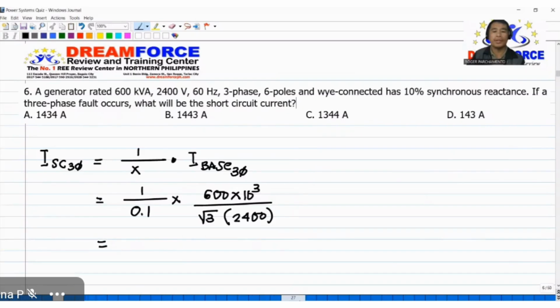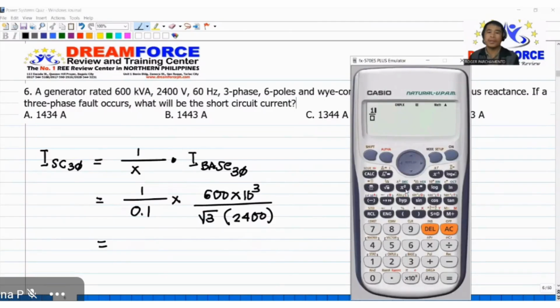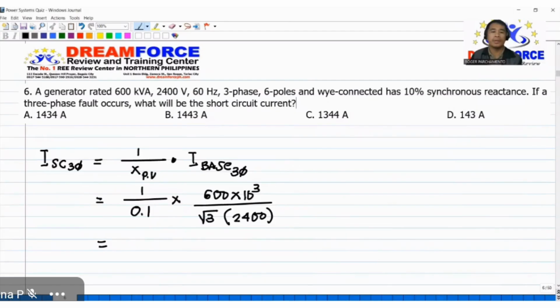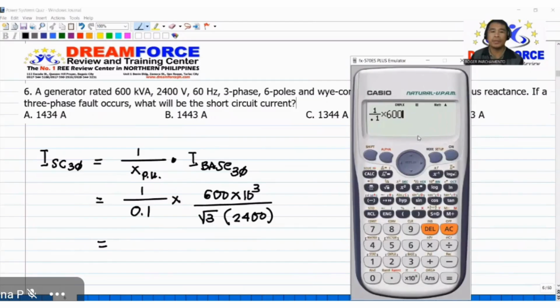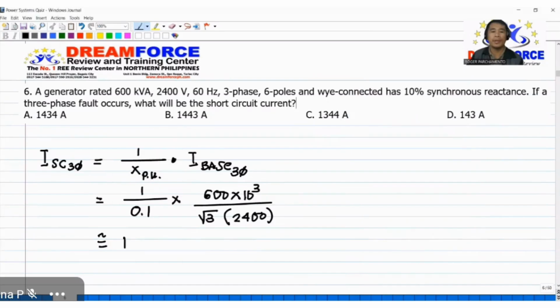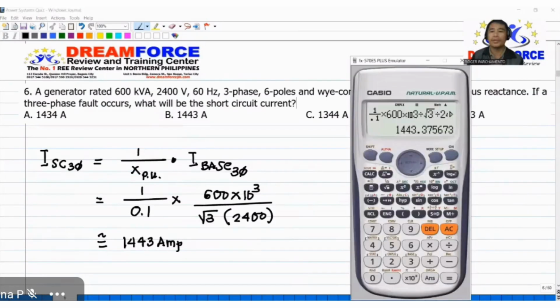So the 3-phase short circuit will be 1 divided by 0.1 times 600. This is per unit, X per unit, positive sequence. Exponent 3 divided by square root of 3 and divided by 2,400 also. So that will be 1443. Approximately equivalent to 1443 amperes. So letter B.